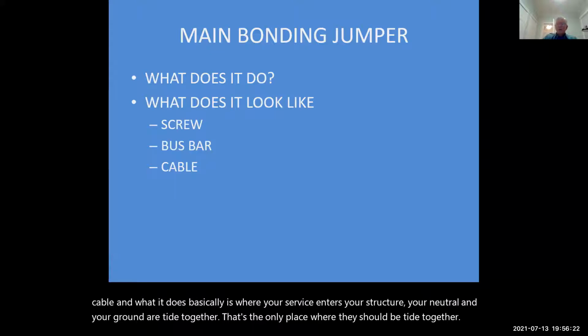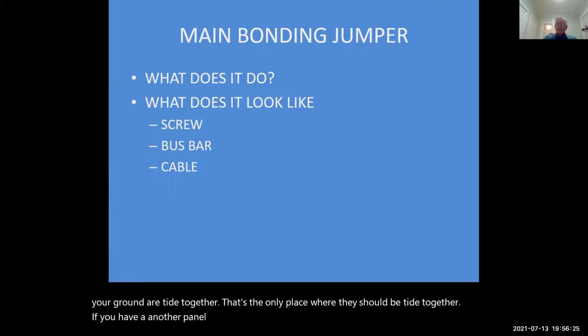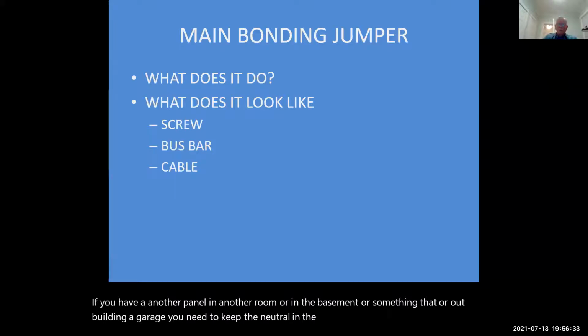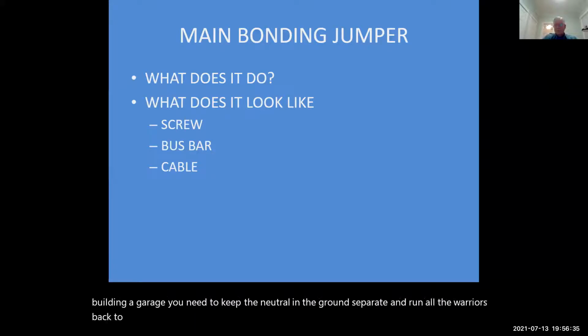If you have another panel in another room or in the basement or an outbuilding or garage, you need to keep the neutral and the ground separate and run all the wires back to the service panel where they're tied together. Again, you want one point where the neutral and the ground are common.